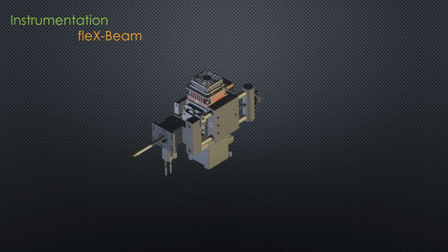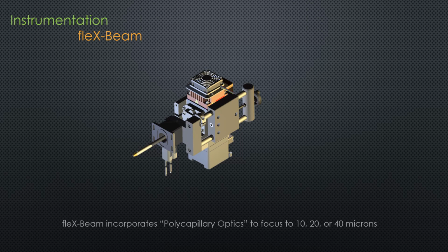Here we have the flex beam. Let's take a closer look. The flex beam incorporates polycapillary optics to focus down to 10 microns. The tube comes as a 40 micron, a 20 micron, or 10 micron focused at the smallest spot. As the tube is moved in and out, the beam can become much, much larger, as much as 25 millimeters or larger if needed.